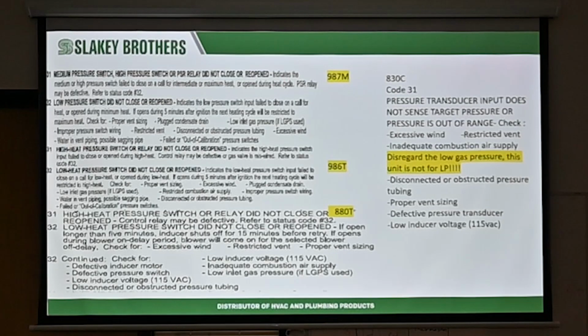All right. Now, the other one is pressure switch did not close. And this is both the medium, the low pressure, or high heat pressure switch. Didn't open or didn't close. You check for power on the switches to see if it's already closed or not. You can unplug them carefully, check continuity. If they're closed, it means a faulty switch or not. But didn't close, that's the most common thing. Something's wrong, my inducer is running, and my switch isn't closing, or my electrical doesn't flow from one spot to the other.